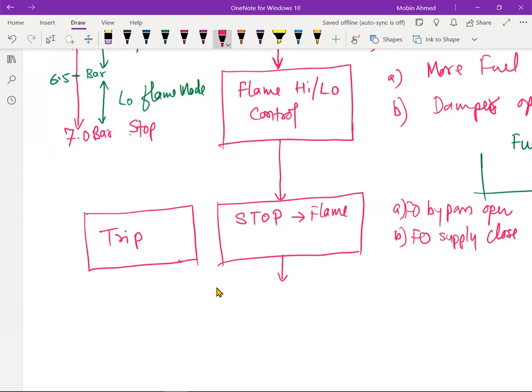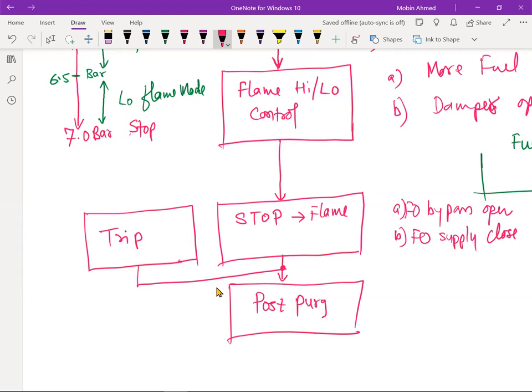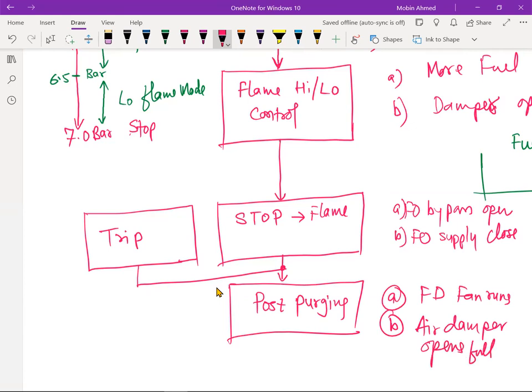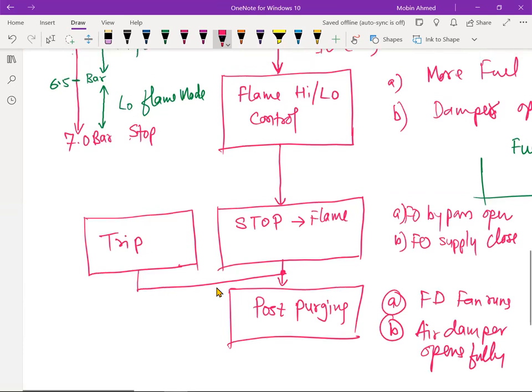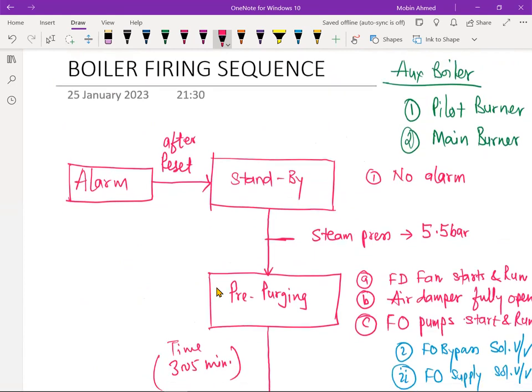And as soon as it is stopped, thereafter it will go for the post purging. In the trip condition also, it will go for the post purging. Remember this one. After the post purging, the FD fan is going to run continuously, the FD fan runs and the air damper opens fully. After the post purging, either it will go to the alarm condition if it is a trip, or if everything is normal, it will go to the standby mode. Okay, so this is the firing sequence.